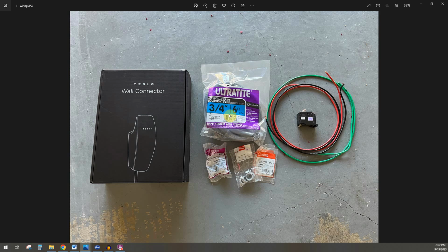It's a plastic PVC mix. You could put it in PVC conduit or EMT, which is the metal tubing that you see on outsides of houses. So there's a variety of conduits you can put it in, but this type of wiring needs to be in conduit. Don't just throw it in the wall because that's not to code, and that's going to cause you problems later. Like if you have rats in your wall, they're going to eat your wiring and it's not going to be good.